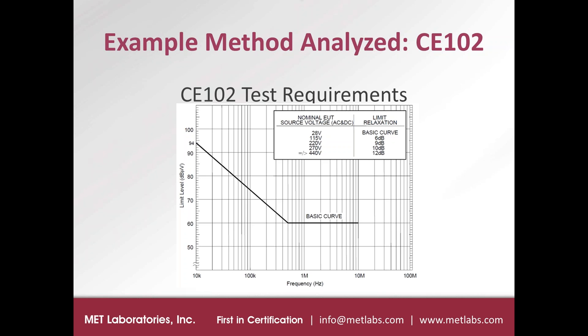And as you can see, there's a relaxation to the curve that's allowed for EUTs operating at different voltage levels. So 28 volt DC powered equipment and anything powered at a voltage lower than that has to meet this basic curve. But then other higher voltages have some relaxation of the limit that's allowed per the table at the top of the limit.